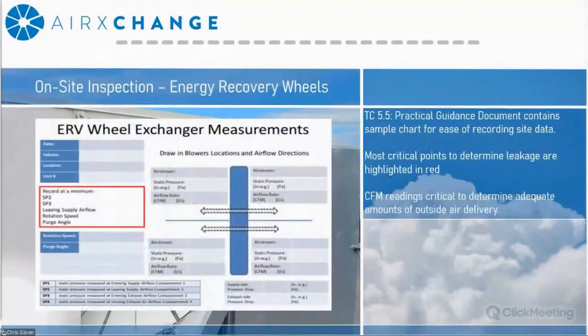So to assist with recording all this information, within the TC 5.5 document, there's a sample chart that you can use for your specific system. The most critical parts in determining leakage are highlighted in the red area. And again, what you're looking for is essentially a more positive pressure in the supply side of the system than the exhaust side of the system. Please keep in mind that if you have certain fan arrangements, both sides of the wheel may be under static pressure, but you just want to make sure that the driving pressure gradient is from the supply side to the exhaust side.